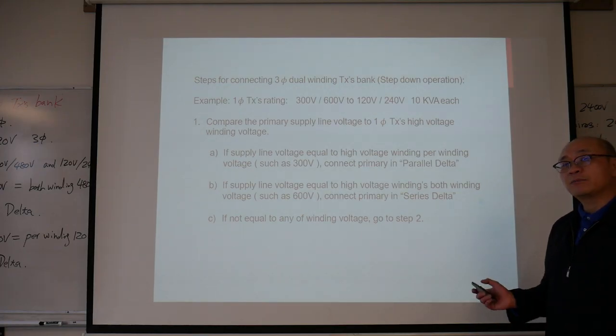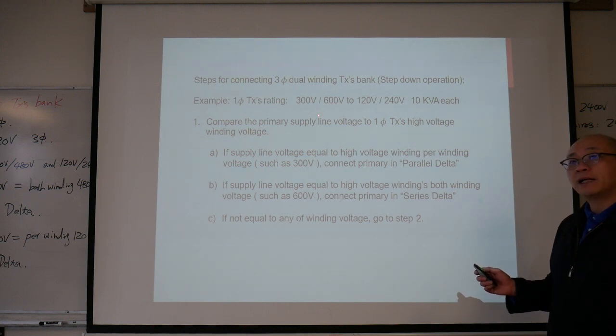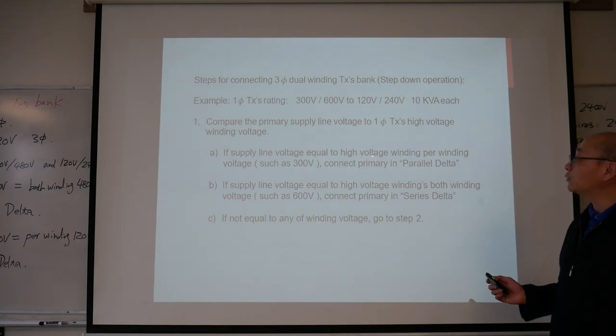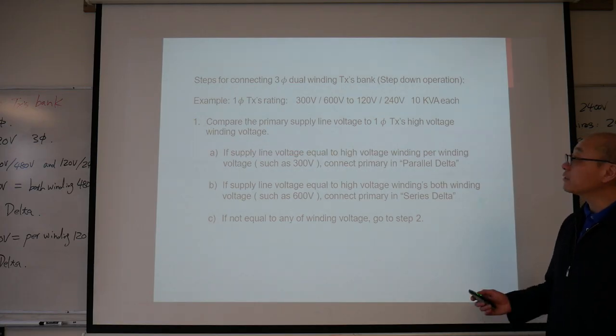First, you're going to check if the primary supply voltage equals any of the high voltage winding ratings. The 300 volt, I will call the per winding rating. 600 volt will be both windings connected in series, so that's called the both winding rating. If the supply voltage equals the per winding voltage, 300 volts, you just connect the primary in parallel delta. If the supply voltage equals the both winding voltage, 600 volt, then you're going to connect the primary in series delta.